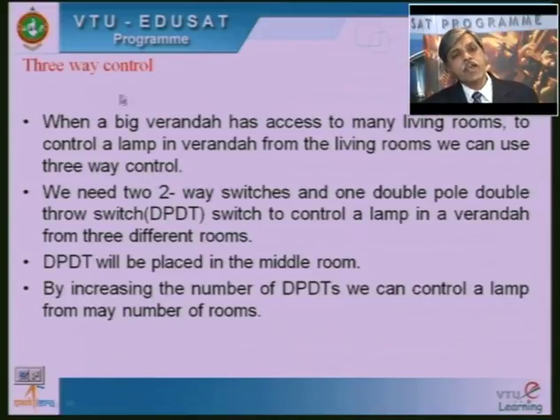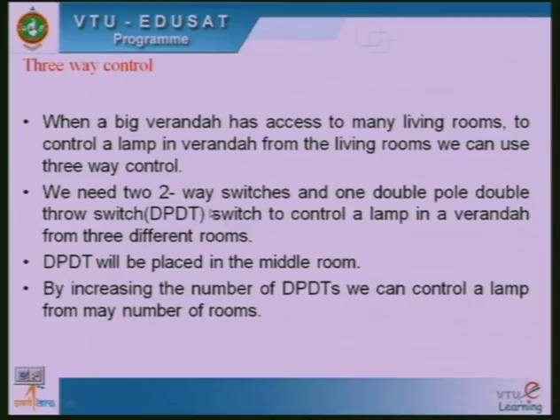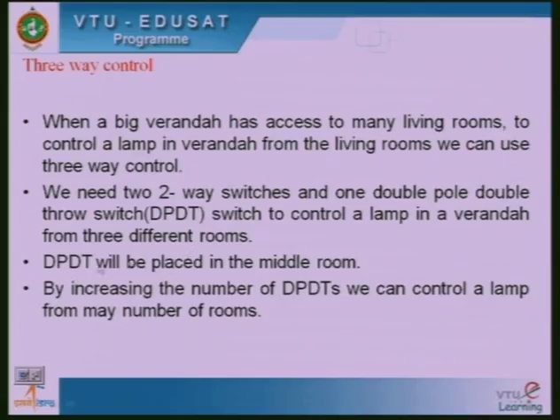In doing this 3-way control, I need 2 two-way switches and 1 double pole double throw switch. What do I mean by a double pole double throw switch? It means I can have this switch closed in both directions, either this direction or the other direction, to control a lamp in a veranda from 3 different rooms. This is called a DPDT, double pole double throw, and will be placed in the middle room.